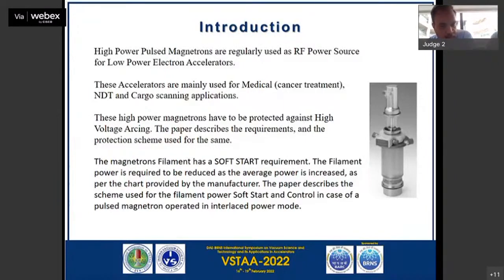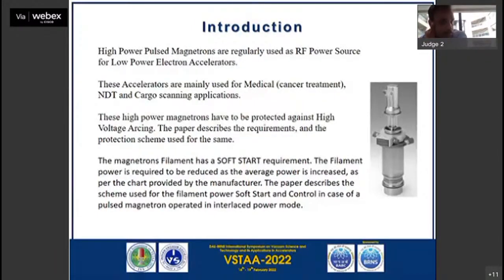One minute left. Secondly, for filament soft start: magnetron is a very funny device. The more the output power, the more the power injected into the magnetron, the more the heating that takes place on the cathode. So the cathode temperature has to be reduced.